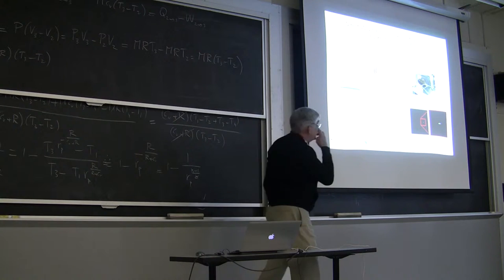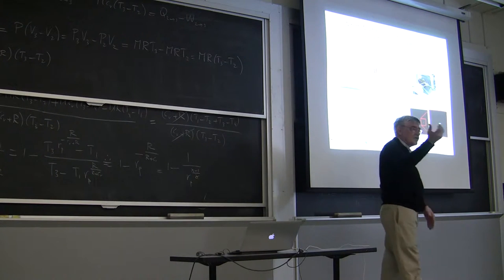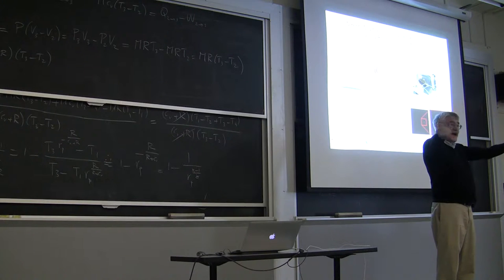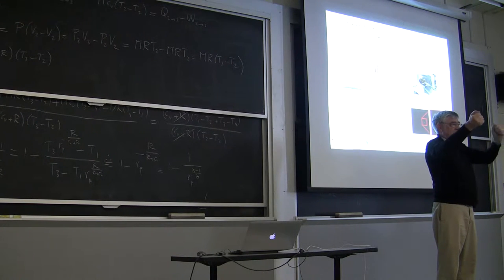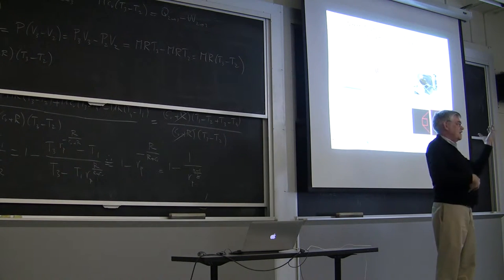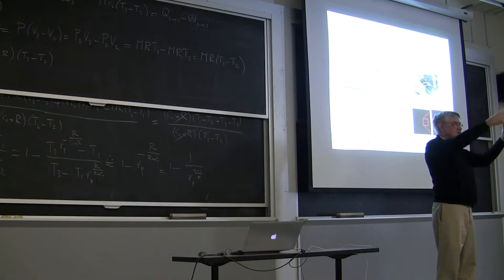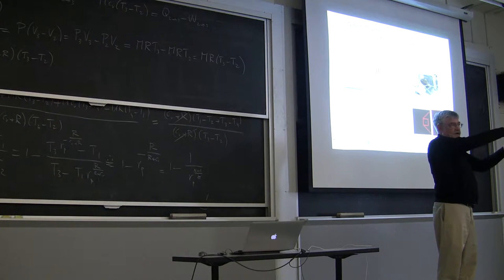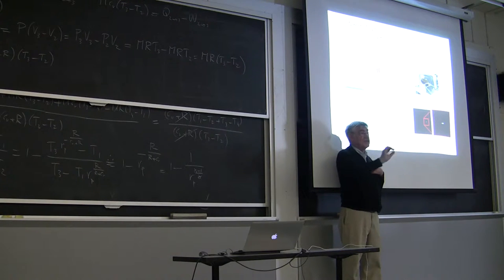Here's another example. Here we're using photoacoustic imaging with ultrasound. And one of the things, if you want to provide one of those augmented reality displays, the standard way of doing that is I track my ultrasound probe. I track, say, a video camera, and I kind of subtract between them. And you have a lot of add-up of errors. Here, if you flash laser light onto the surface of an organ and look at that, it generates photoacoustic spots. So I have ultrasound spots, and I know where in my stereo video they correspond, and I can get sub-millimeter registration that way. So it's a direct closure registration loop through the image guidance that you're then going to use to generate your video overlay.